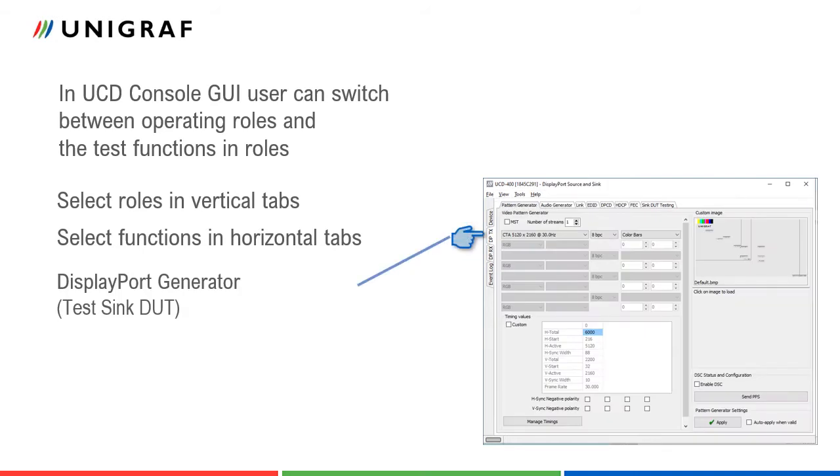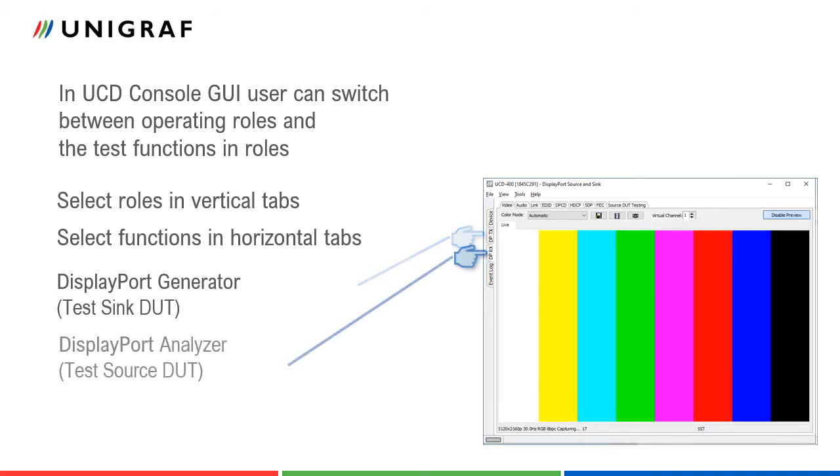Pattern generator role for testing DisplayPort sink devices like monitors and analyzer role for testing DisplayPort source devices like PCs or display controllers. DisplayPort repeater devices can be tested by using the pattern generator and analyzer role simultaneously.